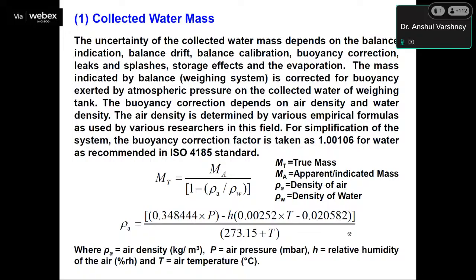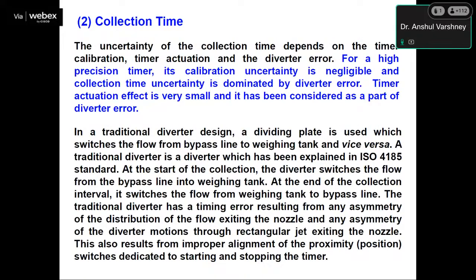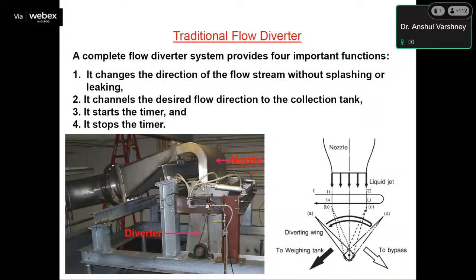The uncertainty of the collected mass basically depends on the balance indication, balance drift, balance calibration, and buoyancy correction also. So you can use it to calculate the density and other things also. The uncertainty of the collection time depends on the timer calibration, timer actuation, and the diverter error. For a high precision timer, its calibration uncertainty is negligible, and collection time uncertainty is dominated by the diverter error. So the diverter basically plays an important role in water flow calibration. So basically, for calculating the flow rate exactly, the diverter error should be as minimal as possible.